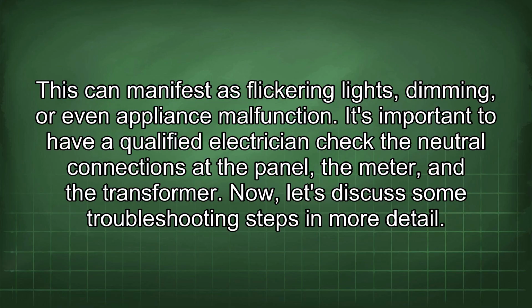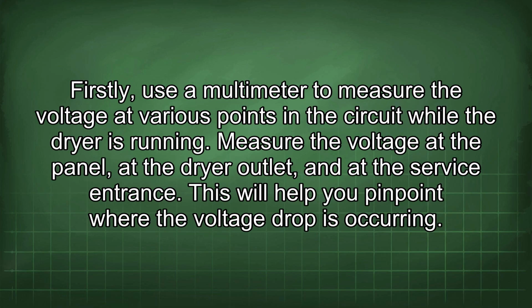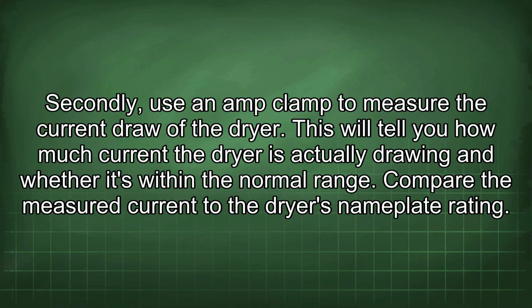Now let's discuss some troubleshooting steps in more detail. Firstly, use a multimeter to measure the voltage at various points in the circuit while the dryer is running. Measure the voltage at the panel, at the dryer outlet, and at the service entrance. This will help you pinpoint where the voltage drop is occurring. Secondly, use an amp clamp to measure the current draw of the dryer. This will tell you how much current the dryer is actually drawing and whether it's within the normal range. Compare the measured current to the dryer's nameplate rating.